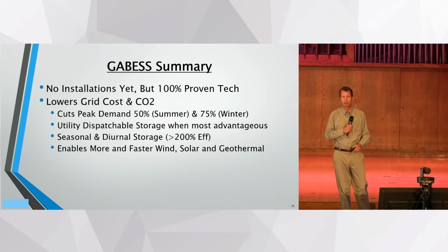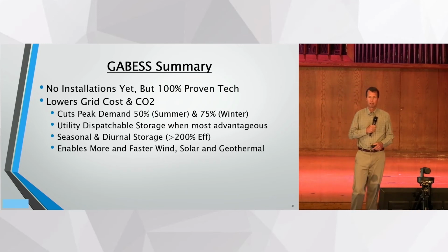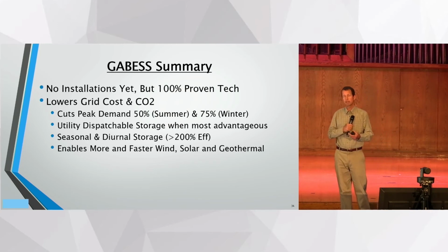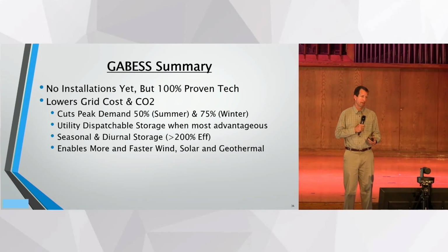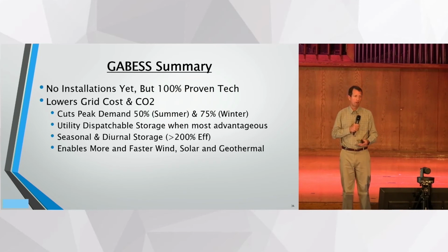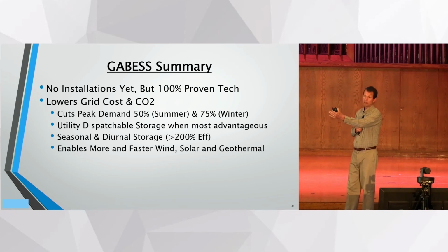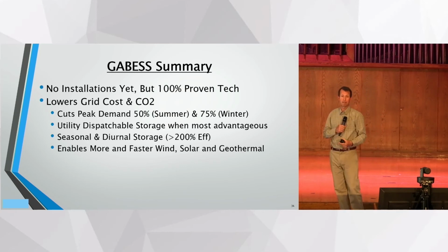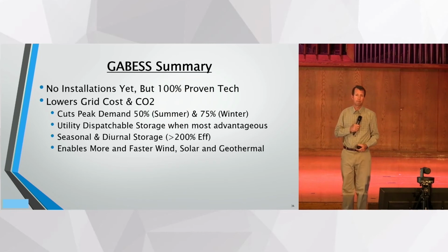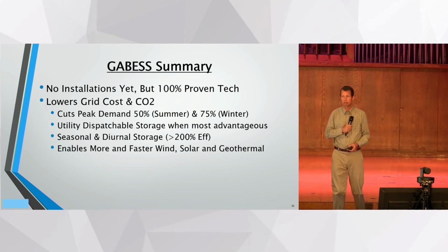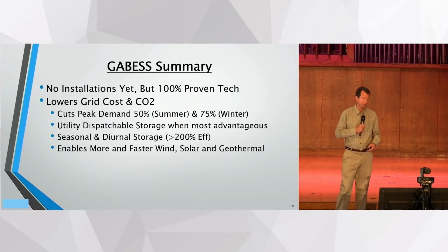All of these things: cutting peaks, avoiding winter peaks, utility dispatchable. So the utility is going to pick when to charge the BTES. If energy costs are really low, even negative, then the utility is going to turn on that chiller and store energy in the ground. If it's really cold, they're going to say, okay, this is a good time to store it. Or they look ahead and say, oh, we've got an extreme weather event coming, it's going to be 110 for 7 days, let's charge up the BTES so that we can build resiliency into the grid. So it makes a lot of sense for this to be a utility-controlled asset.